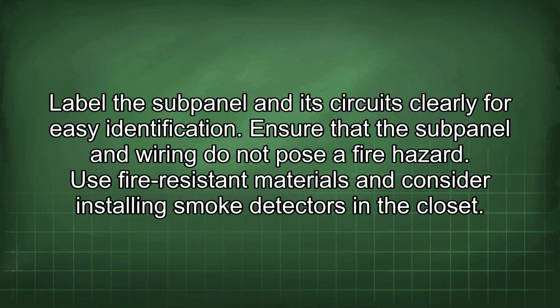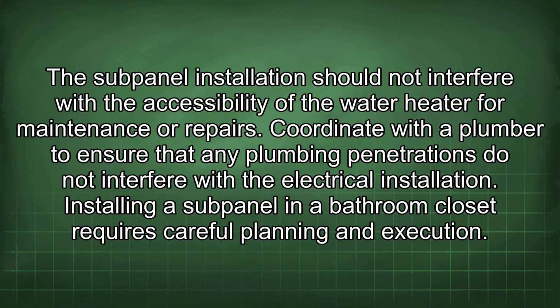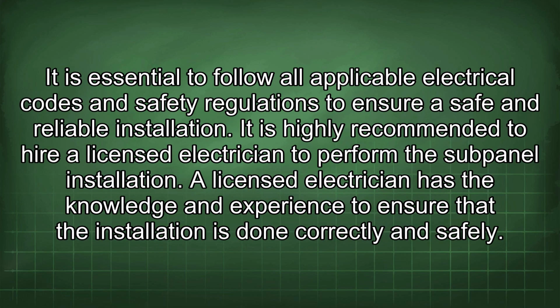Ensure that the subpanel and wiring do not pose a fire hazard. Use fire-resistant materials and consider installing smoke detectors in the closet. The subpanel installation should not interfere with the accessibility of the water heater for maintenance or repairs. Coordinate with a plumber to ensure that any plumbing penetrations do not interfere with the electrical installation. Installing a subpanel in a bathroom closet requires careful planning and execution. It is essential to follow all applicable electrical codes and safety regulations to ensure safe and reliable installation.